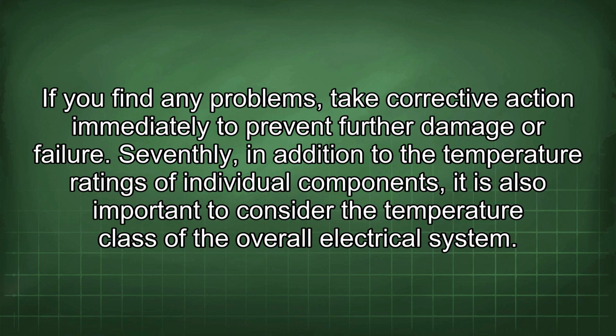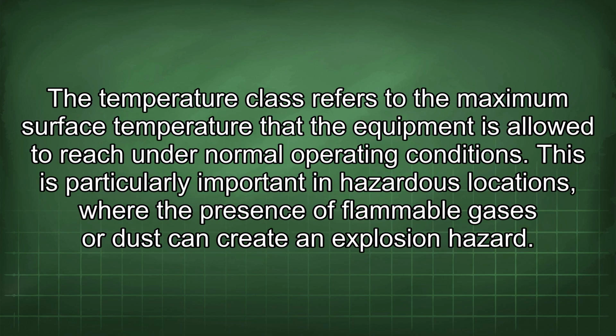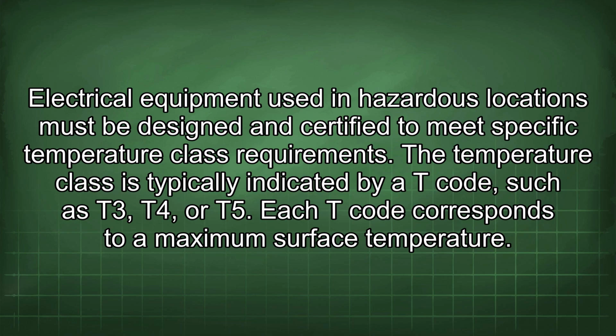Seventhly, in addition to the temperature ratings of individual components, it is also important to consider the temperature class of the overall electrical system. The temperature class refers to the maximum surface temperature that the equipment is allowed to reach under normal operating conditions. This is particularly important in hazardous locations where the presence of flammable gases or dust can create an explosion hazard.